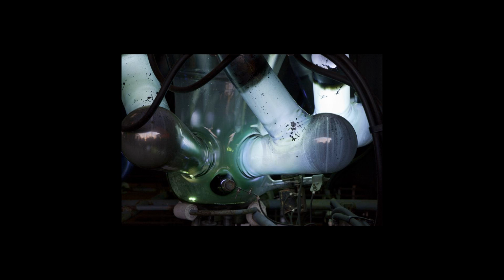Operating principles. Operation of the rectifier relies on an electrical arc discharge between electrodes in a sealed envelope containing mercury vapor at very low pressure. A pool of liquid mercury acts as a self-renewing cathode that does not deteriorate with time. The mercury emits electrons freely, whereas the carbon anodes emit very few electrons even when heated. So the current of electrons can only pass through the tube in one direction, from cathode to anode, which allows the tube to rectify alternating current.